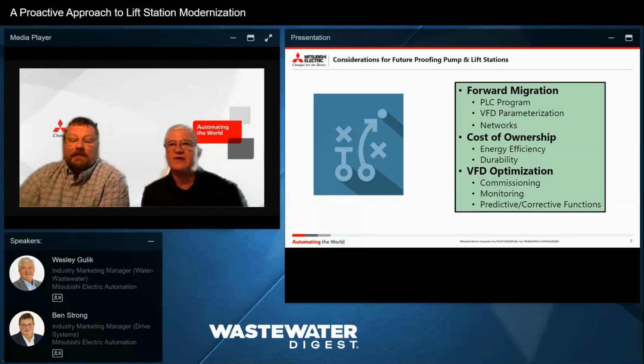And then VFD optimization. We're starting to hear people call the VFD a sensor, and they're becoming smarter and smarter. There's a tremendous amount of data that you can get from the variable frequency drive and send over to a SCADA system to start doing proactive, preventive maintenance. So it's extremely important to utilize the VFD to its full capacity.